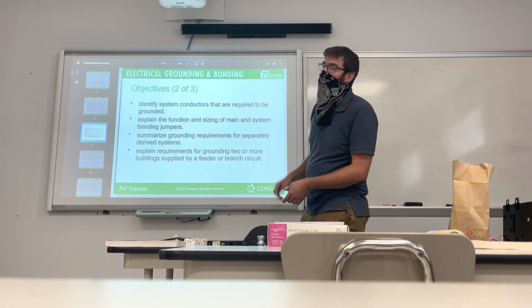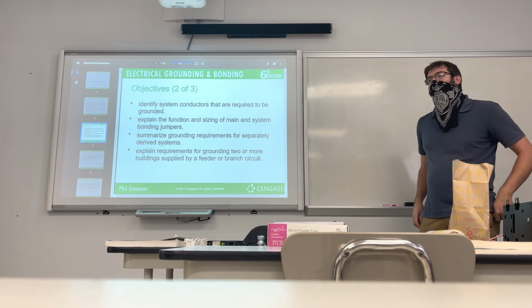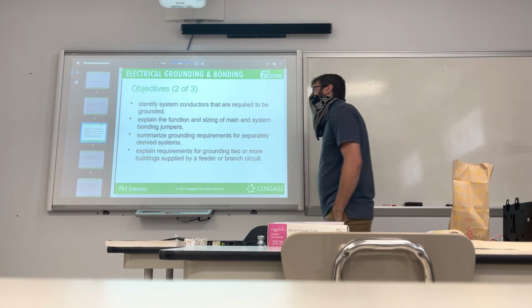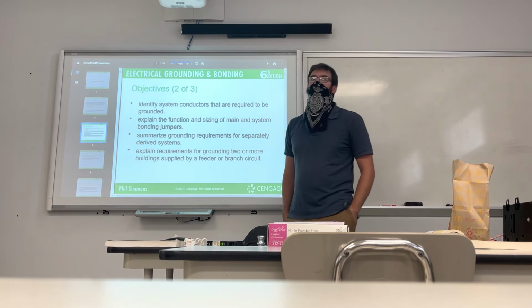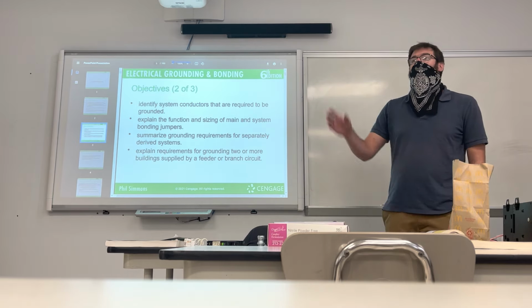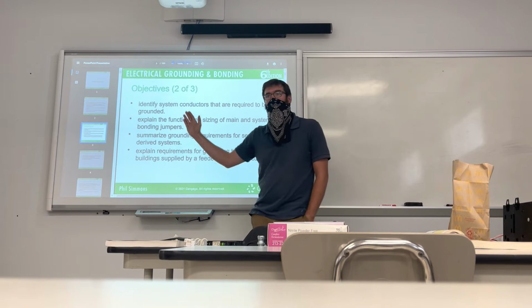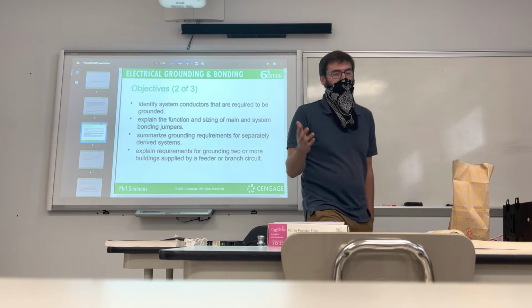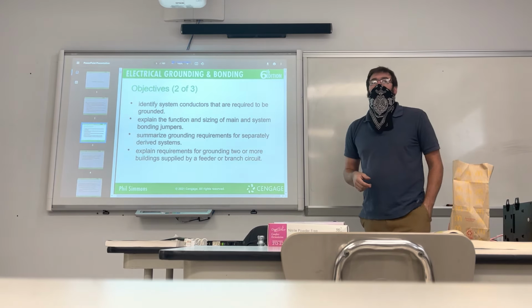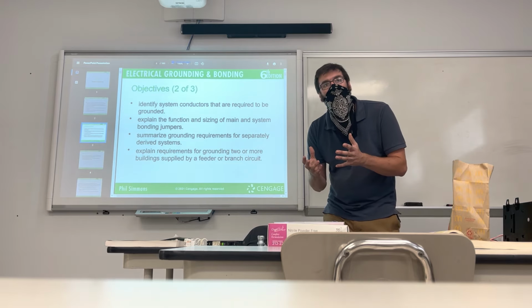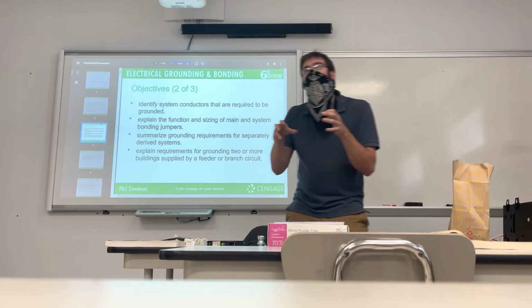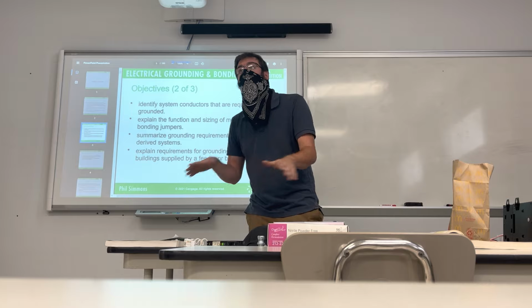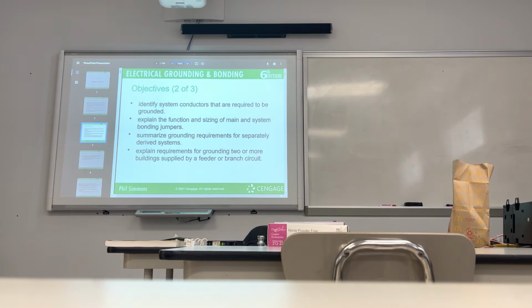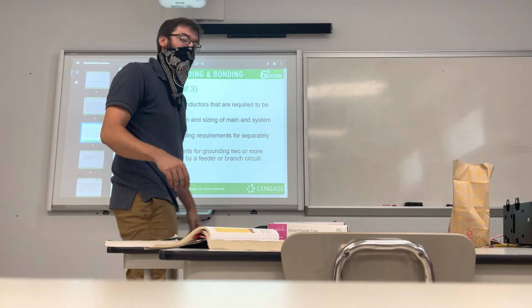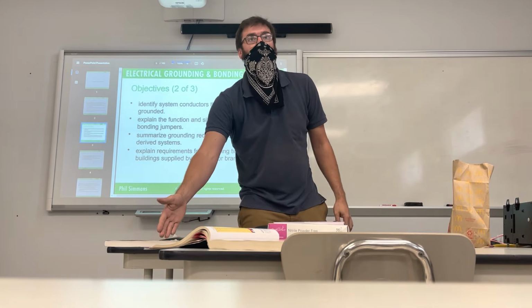All right, so how do we size that, Phil? Like I don't know, number wise, but like you said, doesn't it go off the main, whoever's coming in? If you look in the code book, in the chapter, there will be a scale there that tells you, for the size of power coming in, what your ground conductor has to be. Just like in commercial wiring, Mr. Zarnoff explains how you can measure a box, calculate the cubic inches within the box, and then figure out how many conductors can go in that box, right? You can do all that by math. But this formula right here just tells you that, because somebody already did the math. They wrote it down. There's a reason why we have pencils and pens and paper. If they can do it there, they can do it in this book. And they certainly have. It's very simple.